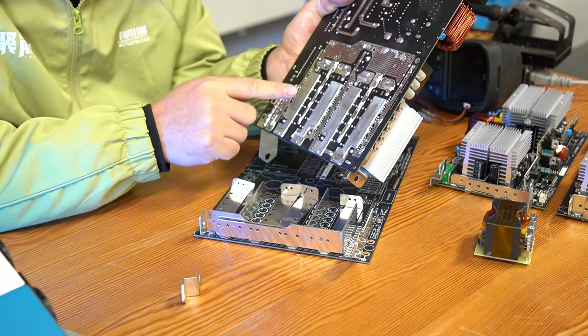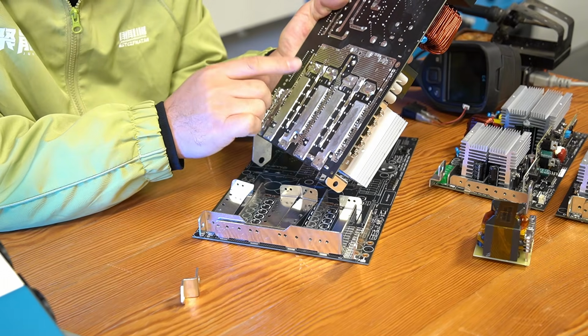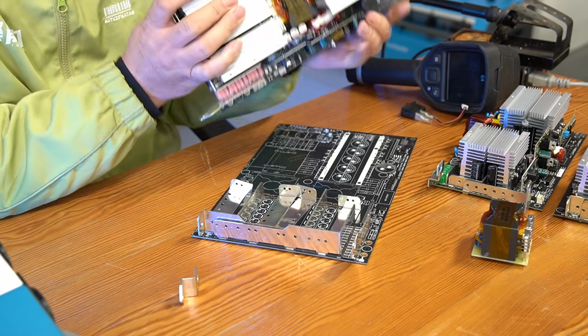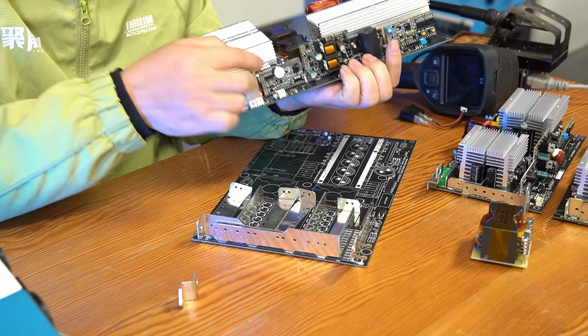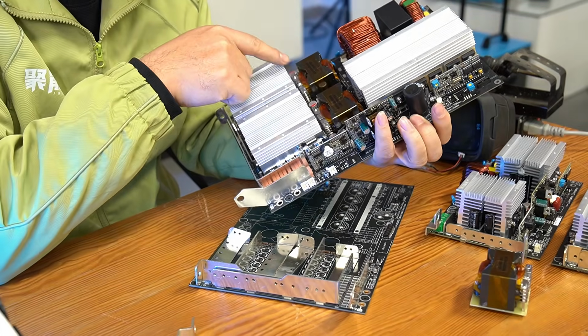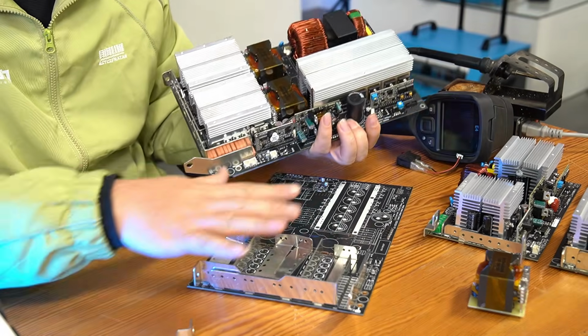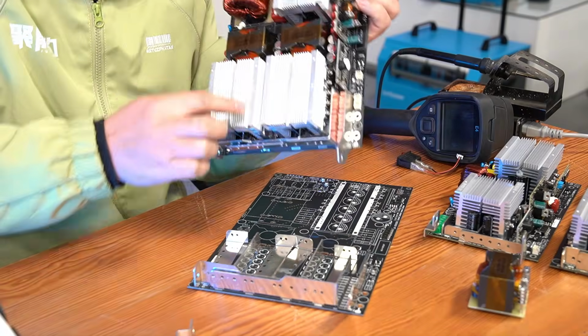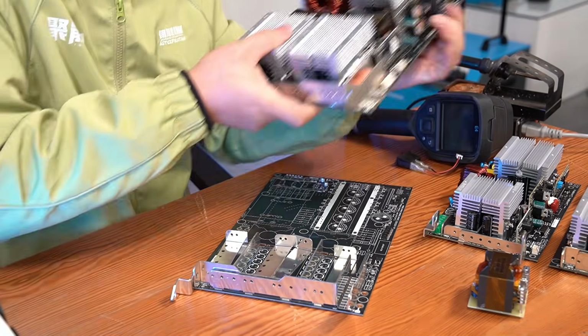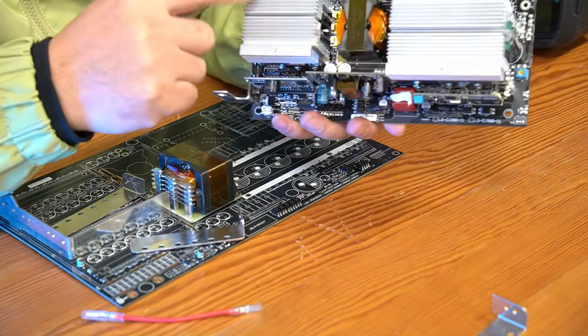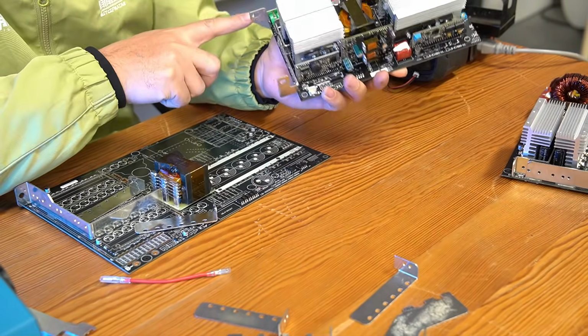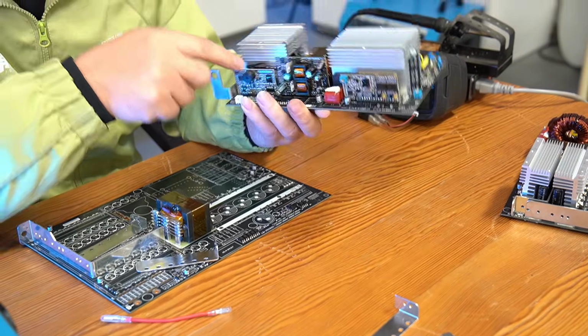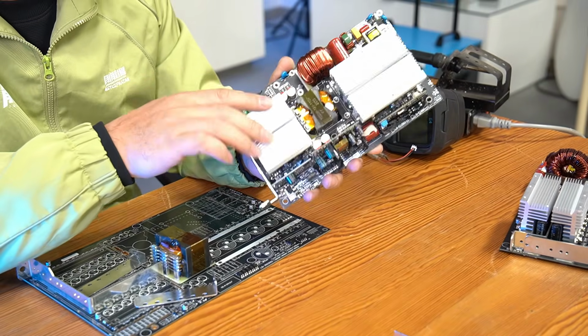A key aspect of our design is that the distance between every 2 transformers is precisely equal. This means the impedance from each transformer to the positive and negative terminals is identical, ensuring balanced power distribution and heat generation among them. Thanks to this symmetrical and direct structure, impedance losses along the current transmission path are minimized.